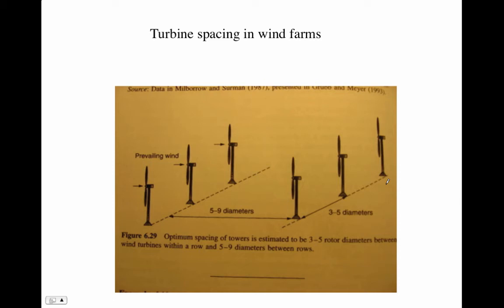For spacing in large wind farms, you can't space the wind turbines too close because there will be a wind shadow and turbulence from one turbine to the other. Typically for 300-foot diameter turbine blades, they'll be five to nine times that diameter apart in rows and three to five times that diameter apart within rows. Then the rows will be offset so a turbine in one row sits between two turbines in the adjacent row. It's much more complicated to site large wind turbines, but that gives you a little idea of the spacing.